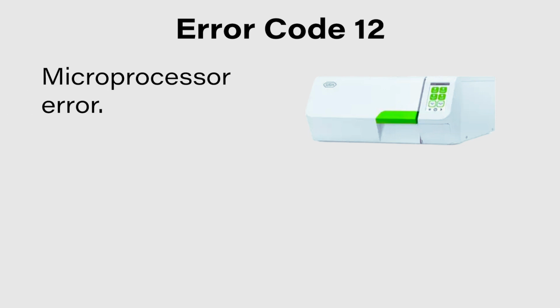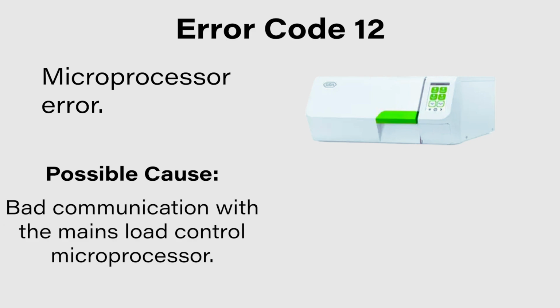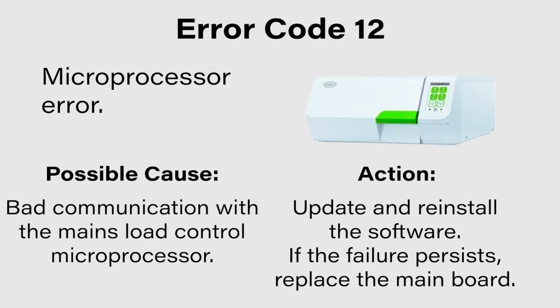If your W&H Lexa Mini Autoclave is displaying an error code 12, that means that there was a microprocessor error. The possible cause is bad communication with the mains load control microprocessor. For this, update and reinstall the software, and if the problem persists, replace the main board.